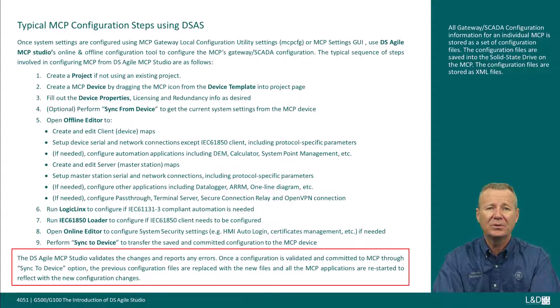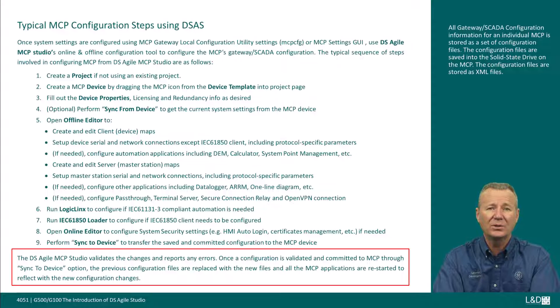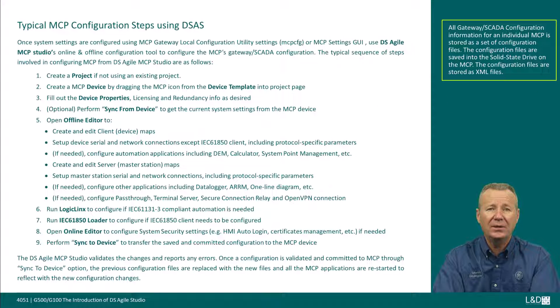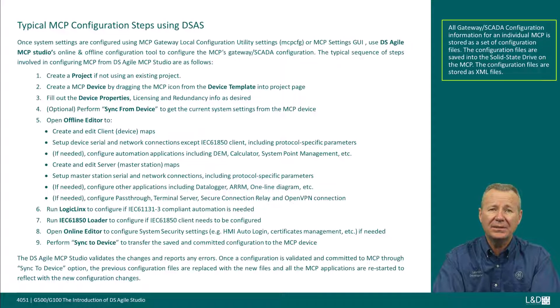DS Agile MCP Studio validates the changes and reports any errors. Once a configuration is validated and committed to the MCP through the sync to device option, the previous configuration files are replaced with new files and all MCP applications are restarted to reflect the new configuration changes. All gateway/SCADA configuration information for an individual MCP is stored as a set of XML configuration files saved into the solid-state drive on the MCP.